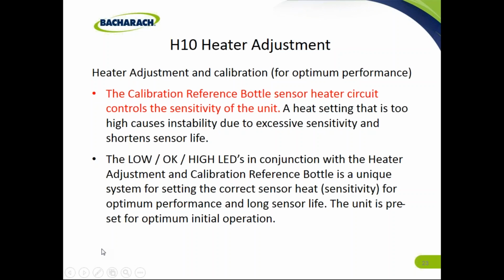So what we're saying here is this unit is really unique. With a lot of refrigerant leak detectors, as you use a sensor more and more, you don't get to adjust that sensor heat, and so it gets less and less sensitive during its life. With this unit, the beauty of the H10 Pro is you can constantly set the heat for that, so it's always operating in the exact calibration that it should be from day one.